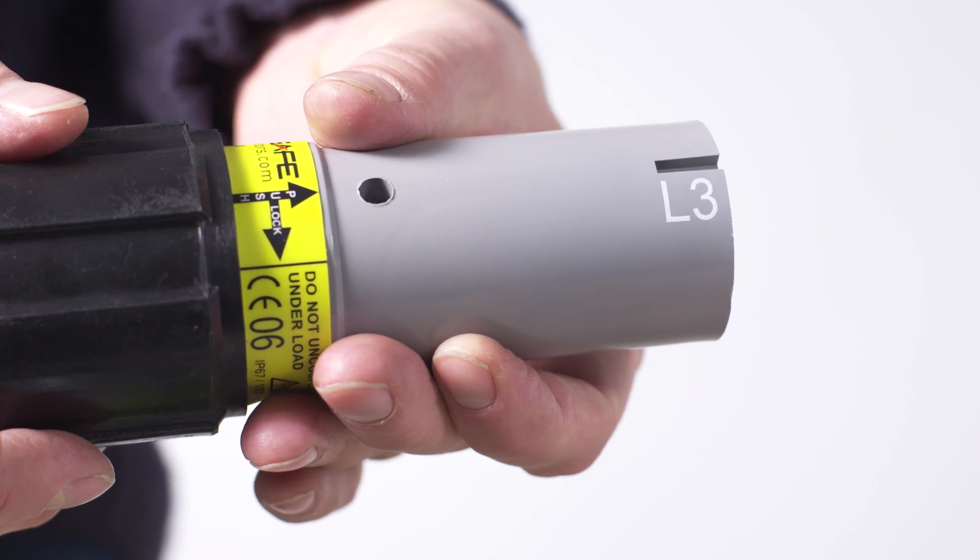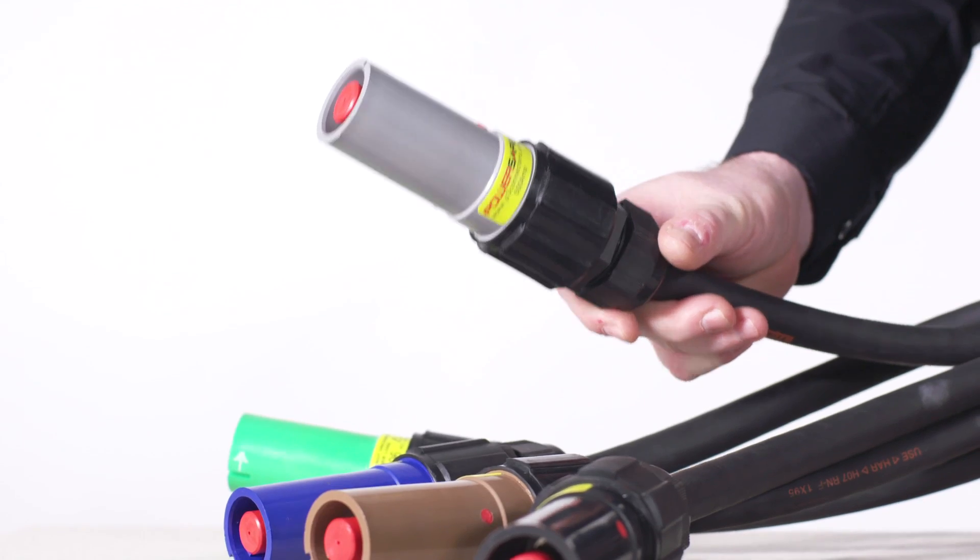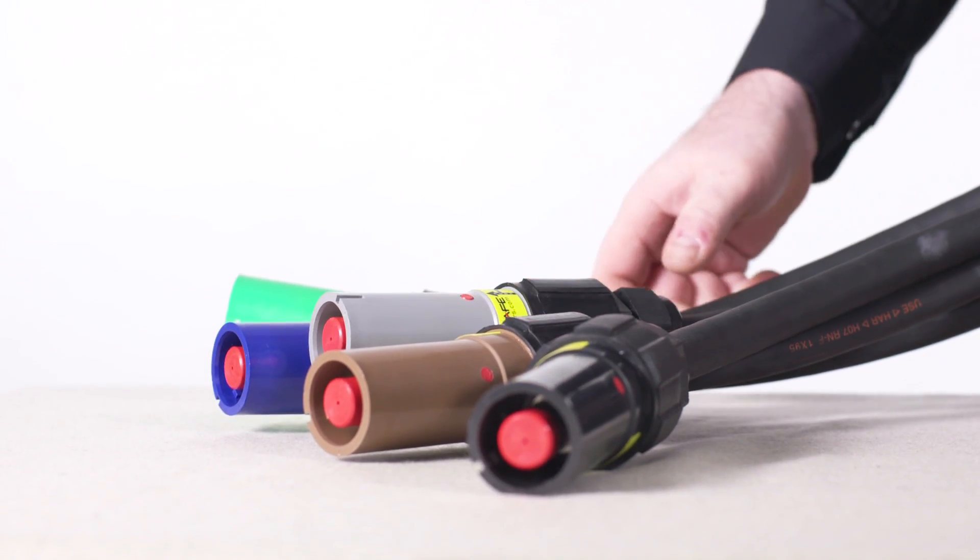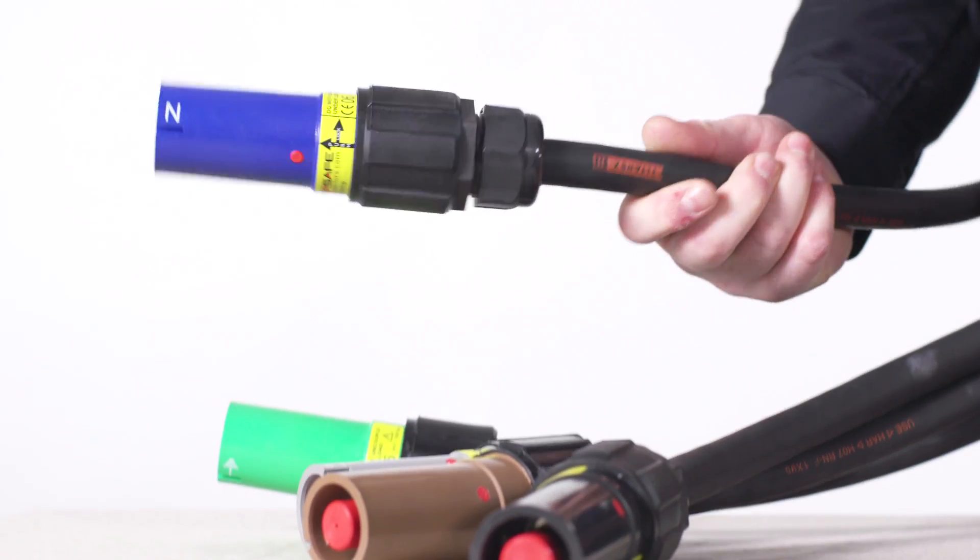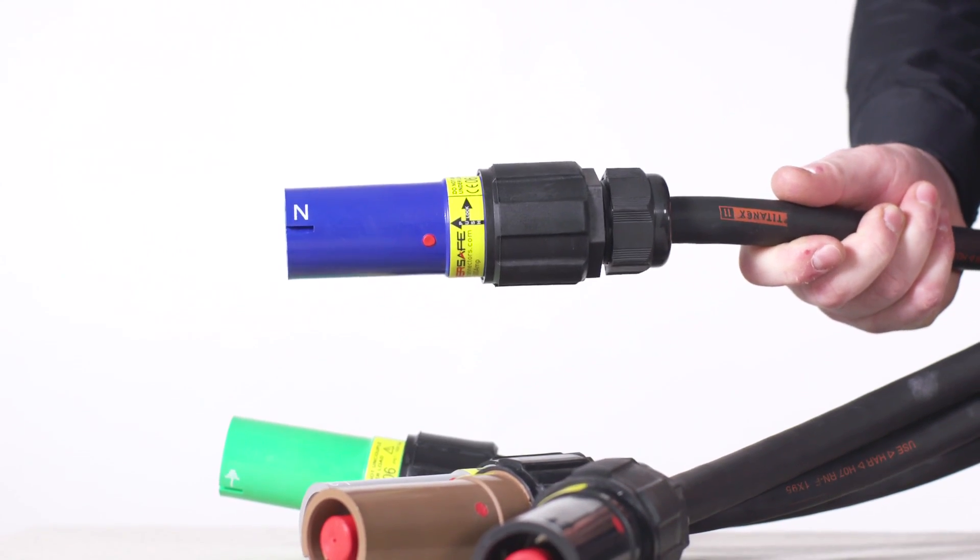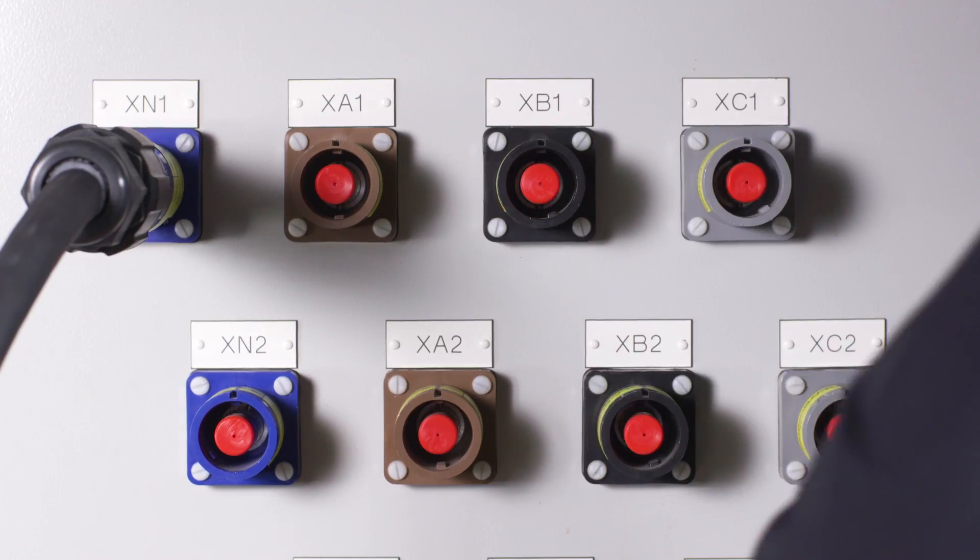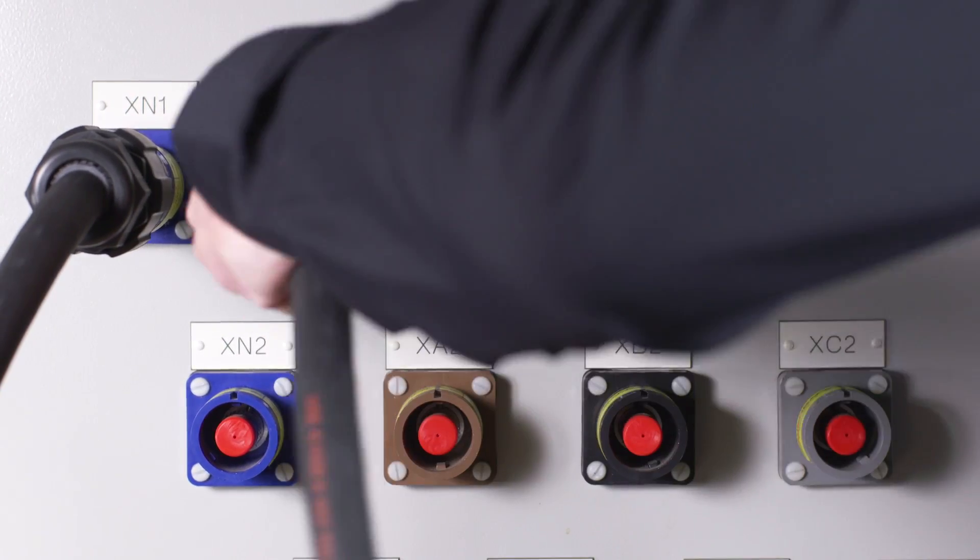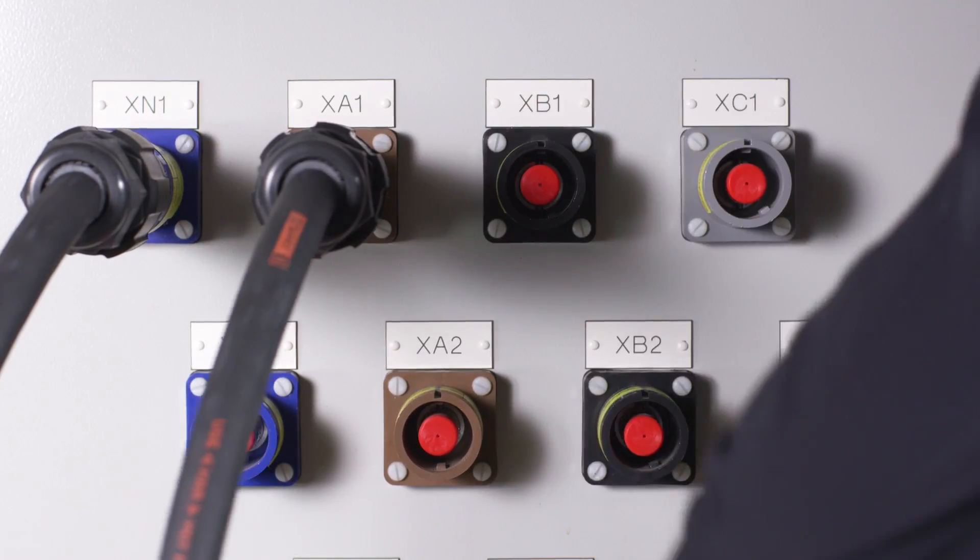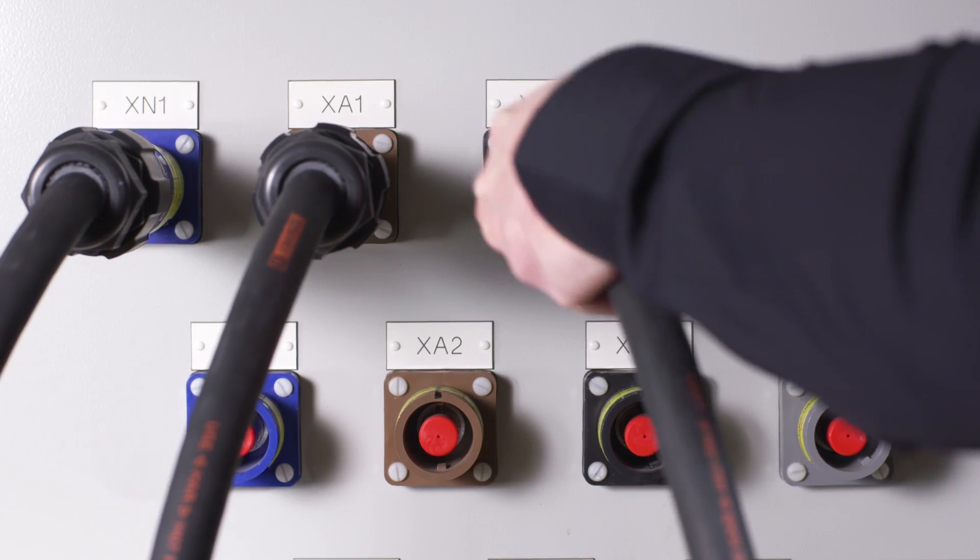All versions can be used for single-phase and much more commonly three-phase applications. Three-phase connections require five separate cables or four if neutral is not required. Single-pole power connectors are employed for making electrical power connections where multi-pole connectors and cables would be impractical to handle due to size, weight and cable bend radius.